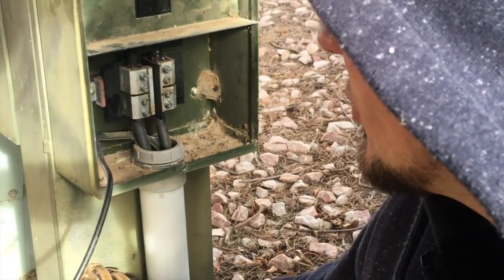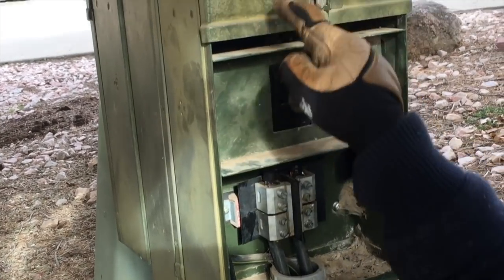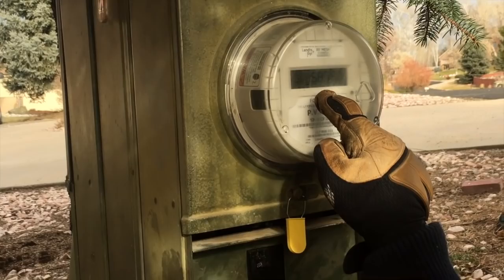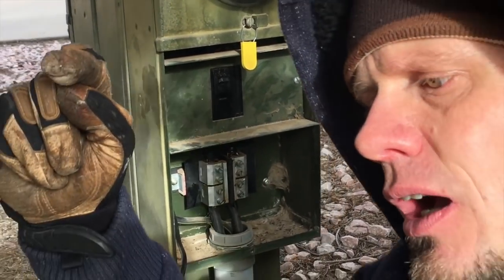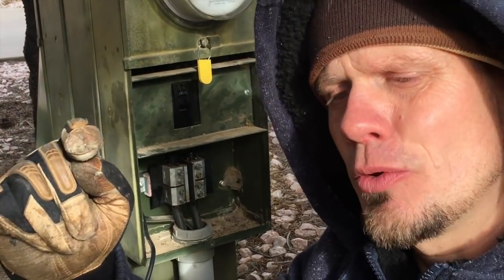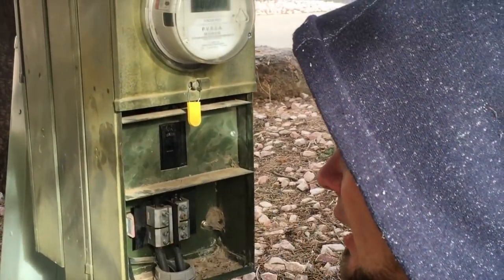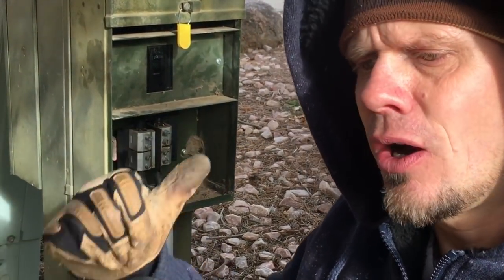This area became energized at equal potential with its own ground rod. When I opened the cover, there was no neutral wire from the meter to the lug in the center of the meter socket — it had been missing for 19 years. REA came out and couldn't believe it. They went in and installed a number 2 aluminum wire with Deox compound. But when I went back in as they were wrapping up, the situation actually got worse — lights started popping.